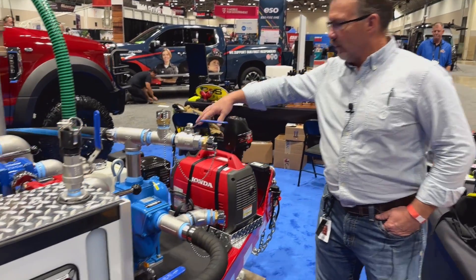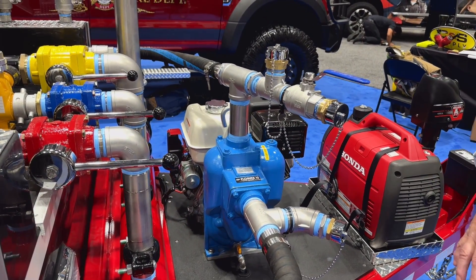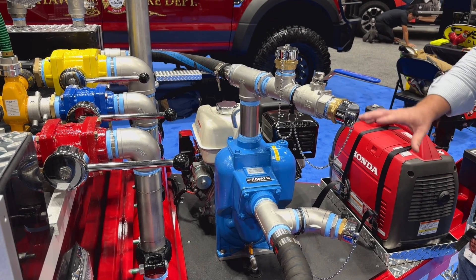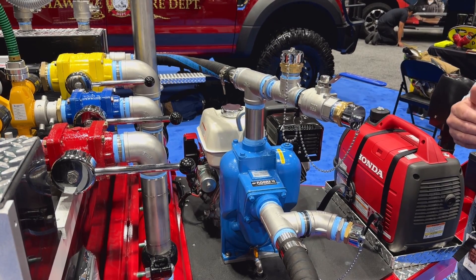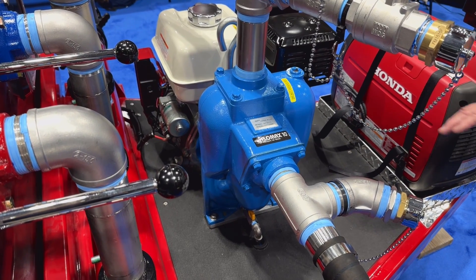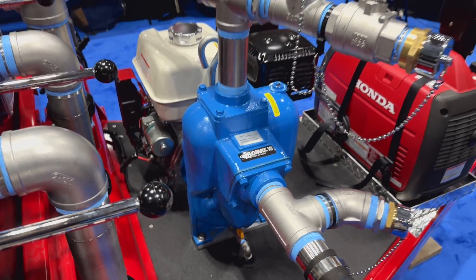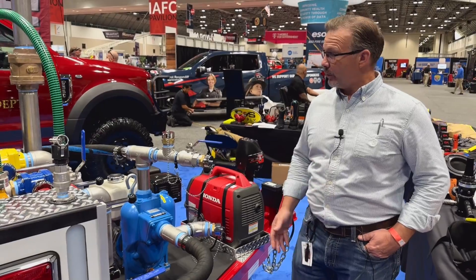We also have a pump here on the front. This is part of a learning curve for our firefighters, because they're used to starting pumps on fire trucks and want to start it up when they see it. But really all this pump does is serve as a fancy onboarding and offboarding pump for the F-500 that we use in this system. It doesn't add pressure — although Weiss Fire could build a system that does — because we already have plenty of pressure at the power plant.